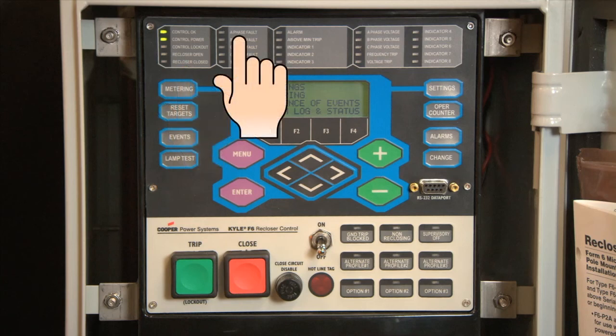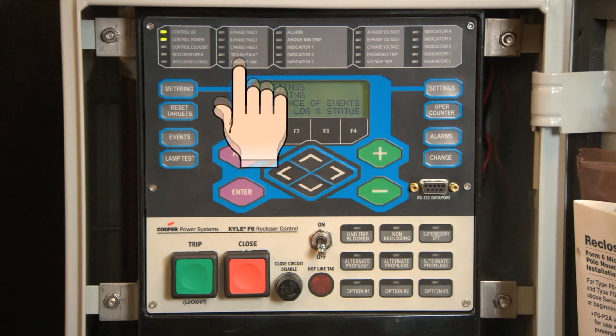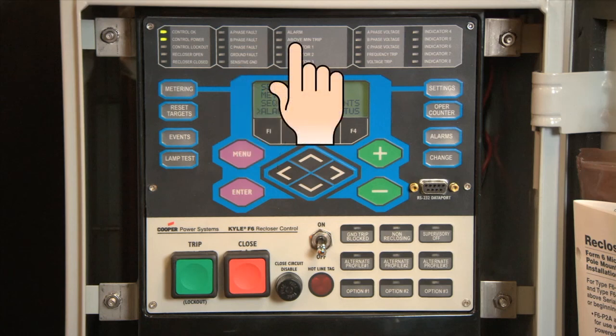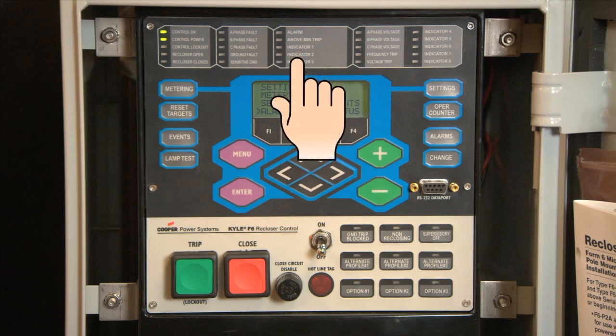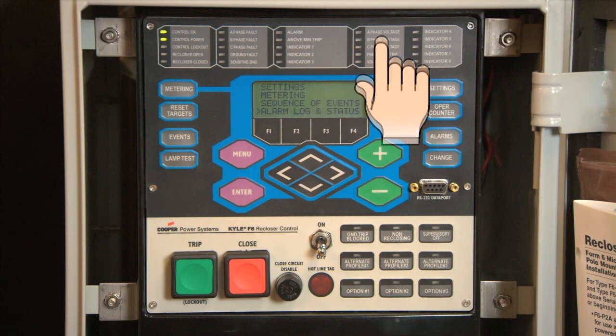Next, we have the phase fault indicators: A phase fault, B phase fault, C phase fault, ground fault, and sensitive ground fault. These will illuminate to identify which phase caused the lockout trip. Sensitive ground fault is currently not used in the programming of these controls. Alarm. This will illuminate and flash should a control or recloser malfunction occur. The minimum trip indicator will illuminate if the current rises above the minimum trip. This will occur while the trip is in process. The indicators 1, 2, and 3 are currently not used in this process. In the next column, we have phase voltage A, phase voltage B, and phase voltage C.